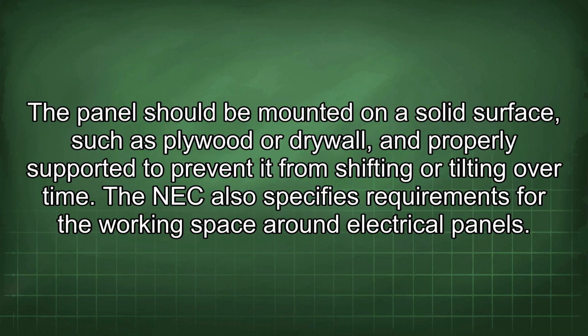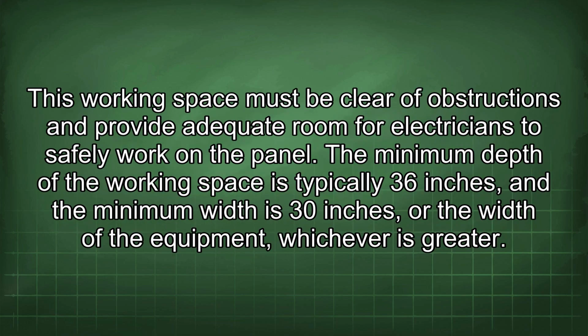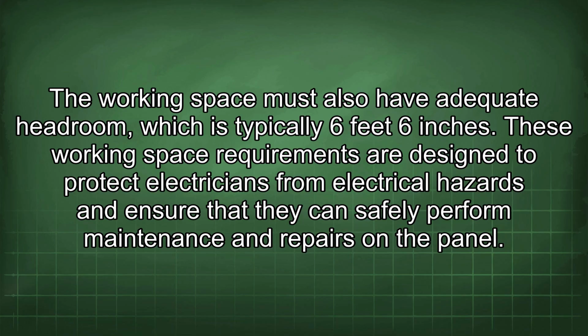The NEC also specifies requirements for the working space around electrical panels. This working space must be clear of obstructions and provide adequate room for electricians to safely work on the panel. The minimum depth of the working space is typically 36 inches, and the minimum width is 30 inches, or the width of the equipment, whichever is greater. The working space must also have adequate headroom, which is typically 6 feet 6 inches. These working space requirements are designed to protect electricians from electrical hazards and ensure that they can safely perform maintenance and repairs on the panel.